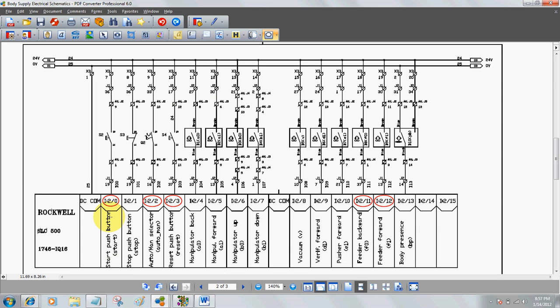Let's look at those same devices in schematic form. The start push button I:2/0 is a normally open push button because that's how it's actually wired in the field. I:2/1 is a normally closed push button, as wired in the field. I:2/2 is the auto/manual selector switch with two positions — in one position it sends a signal to the PLC; in the other position it won't. I:2/3 is the reset push button, wired normally open. The inputs on the actual actuators include I:2/11 and I:2/12, which are feeder backward and feeder forward.